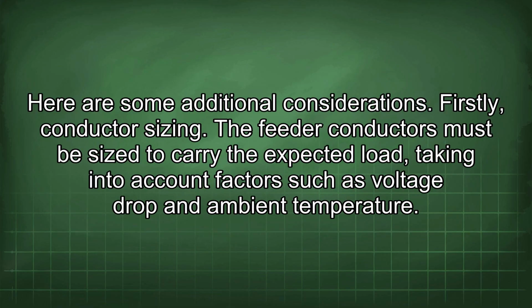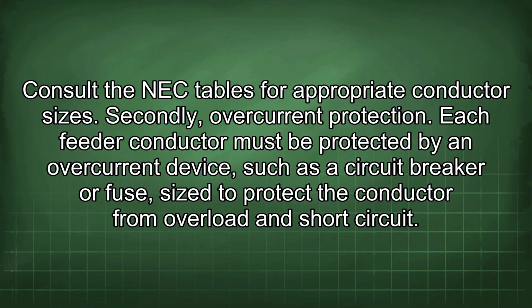Here are some additional considerations. Firstly, conductor sizing. The feeder conductors must be sized to carry the expected load, taking into account factors such as voltage drop and ambient temperature. Consult the NEC tables for appropriate conductor sizes. Secondly, overcurrent protection. Each feeder conductor must be protected by an overcurrent device such as a circuit breaker or fuse, sized to protect the conductor from overload and short circuit.